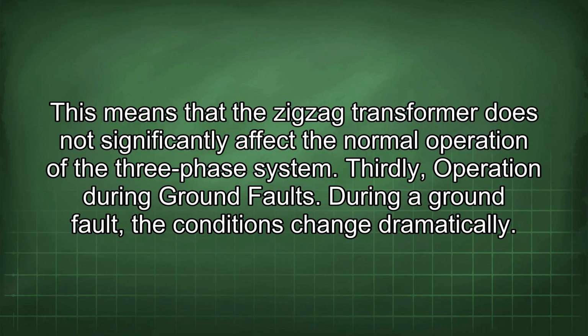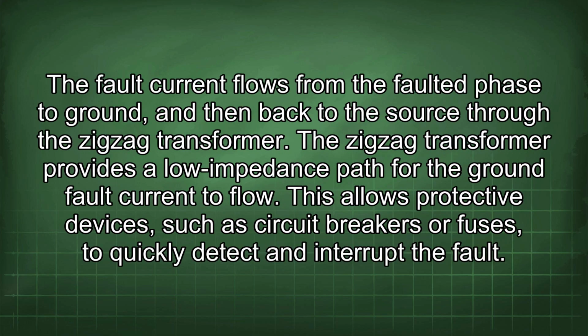Thirdly, operation during ground faults. During a ground fault, the conditions change dramatically. The fault current flows from the faulted phase to ground, and then back to the source through the zigzag transformer. The zigzag transformer provides a low impedance path for the ground fault current to flow. This allows protective devices, such as circuit breakers or fuses, to quickly detect and interrupt the fault.